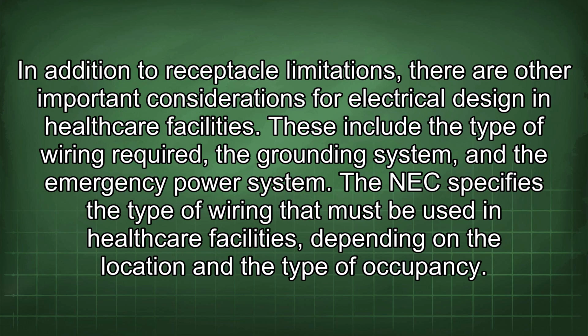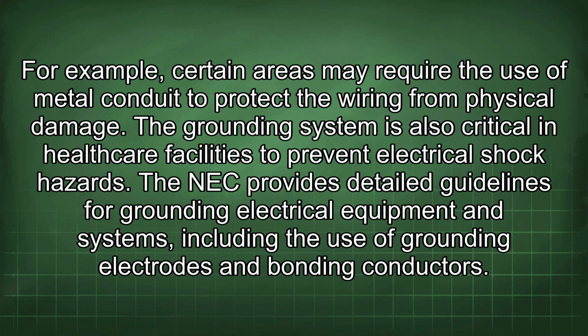These include the type of wiring required, the grounding system, and the emergency power system. The NEC specifies the type of wiring that must be used in healthcare facilities, depending on the location and the type of occupancy. For example, certain areas may require the use of metal conduit to protect the wiring from physical damage. The grounding system is also critical in healthcare facilities to prevent electrical shock hazards. The NEC provides detailed guidelines for grounding electrical equipment and systems, including the use of grounding electrodes and bonding conductors.